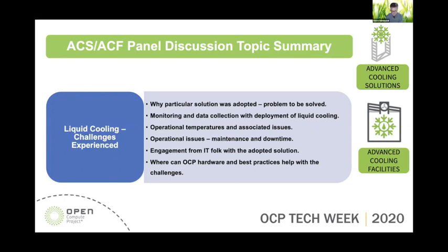So liquids by far give you the best option as a working fluid. Liquids provide distance, and they allow you to capture waste heat at higher temperatures than if you were strictly air cooled. The only way to reuse it is to use liquid cooling as your primary way of keeping your servers cooled. Exactly, I think that's one of the great arguments for it.